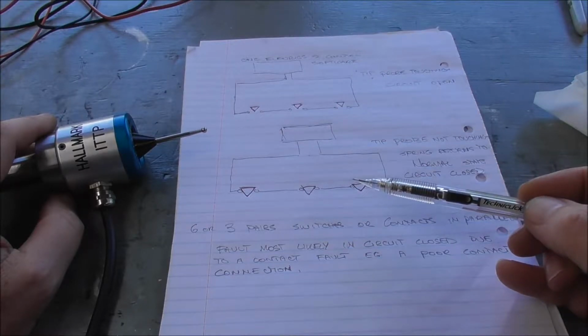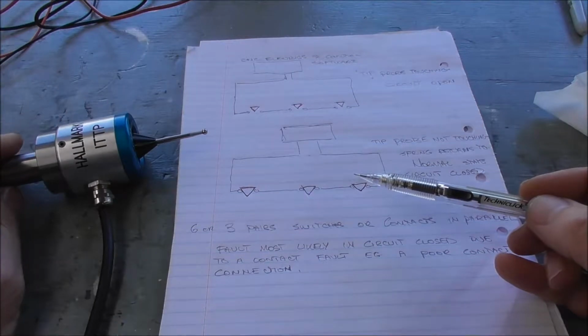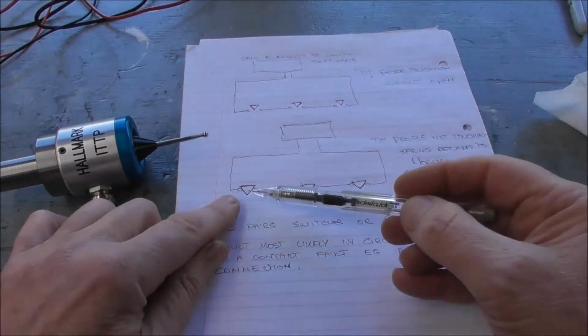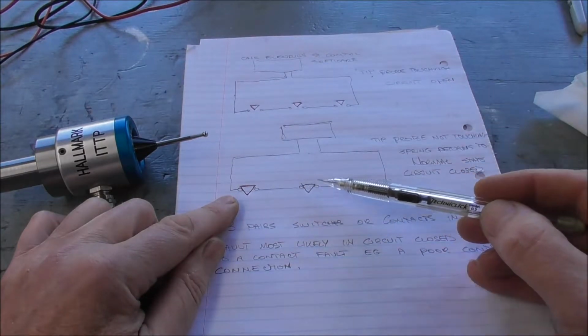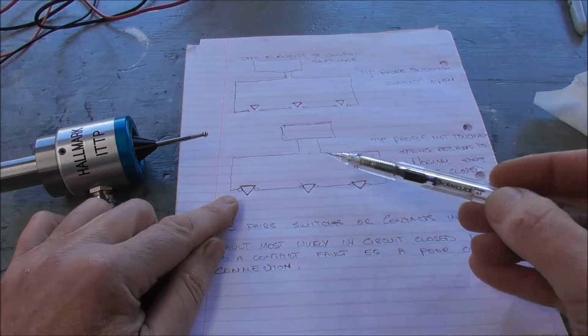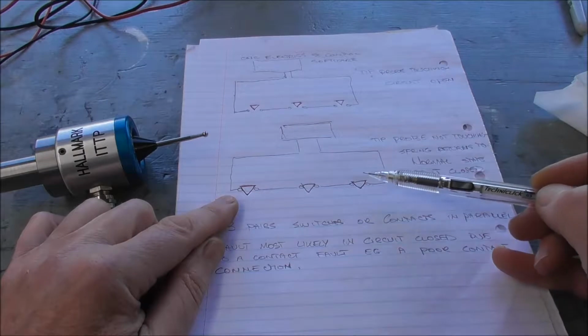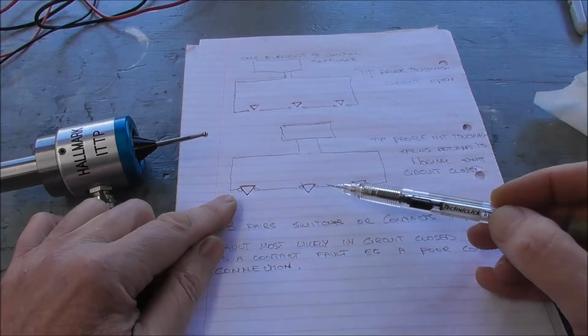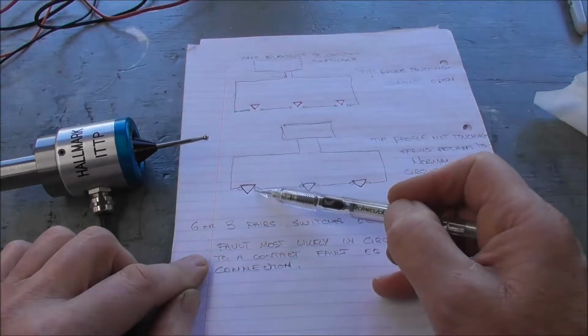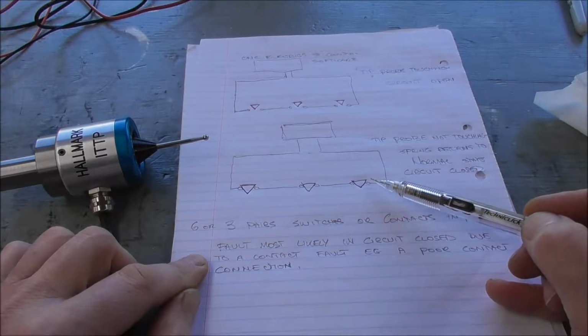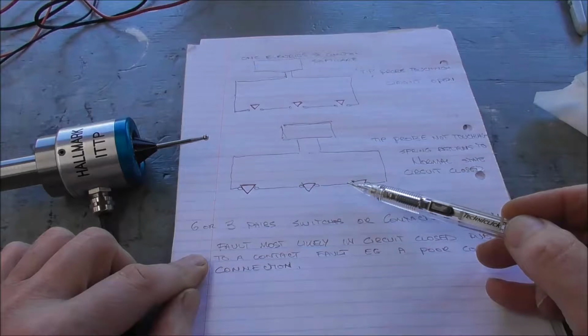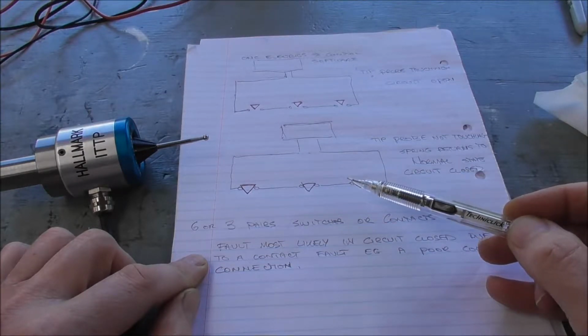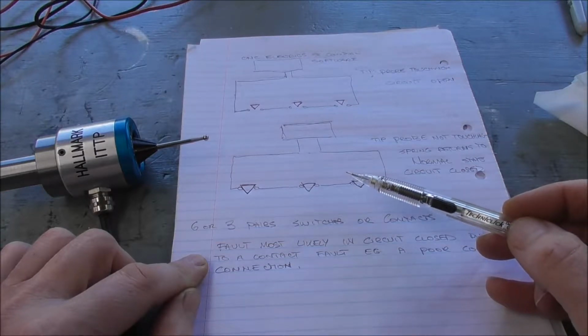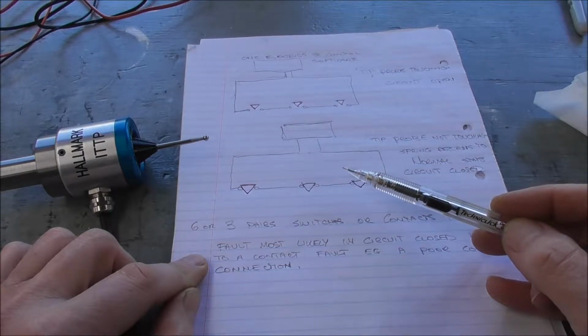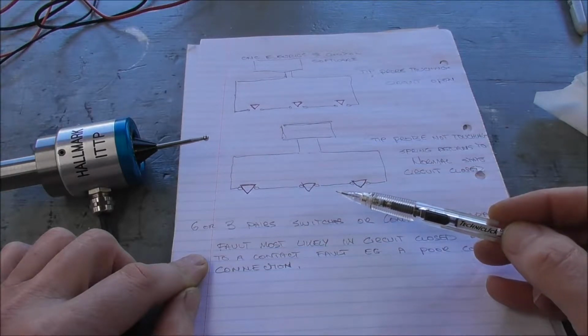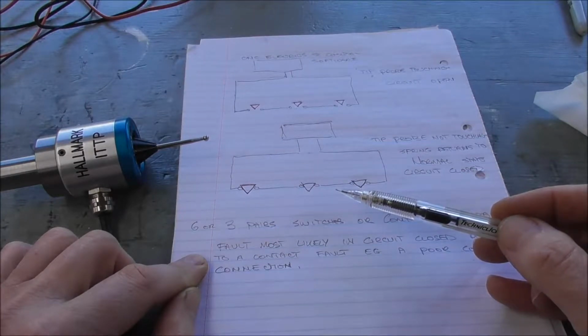We haven't had any faults, but sooner or later there will be a problem, and it's most likely to be in the circuit closed situation. Here in its normal state, all the 6 contacts are closed and there's continuity of current flow. It's most likely to be a fault in that circuit due to one of the contacts being at fault. In other words, a poor connection on one of the 6 contacts, and that could be due to a piece of dirt or dust or fluff or hair between the contacts. That is probably the most likely thing that would happen, and in that case you'd refer to the section in the operator's manual on how to clean out the inside of the probe and the contacts and reinstall the ITTP fluid or gel.